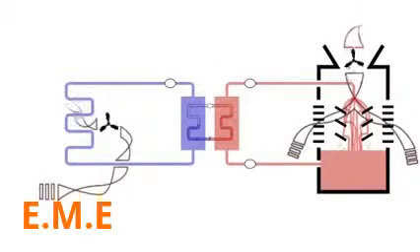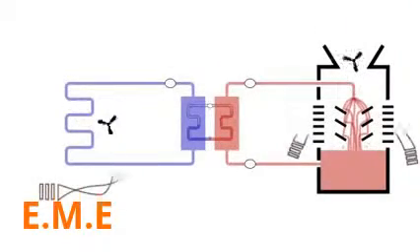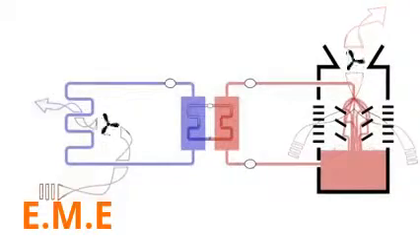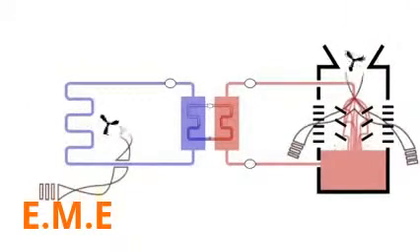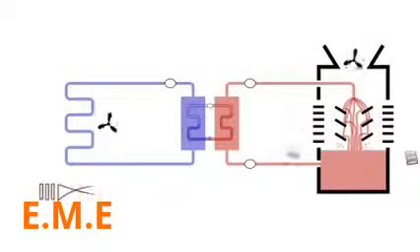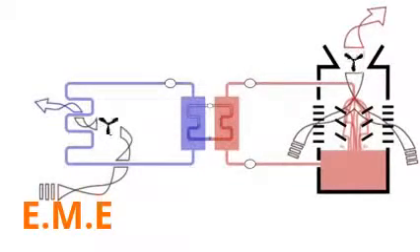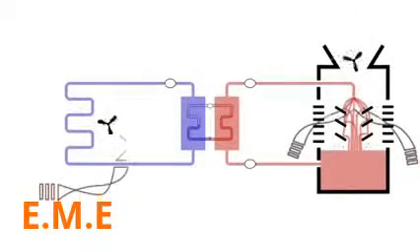This distribution network using water is complicated, but not exceptionally complex. Let's review. Water is cooled by the evaporator and distributed to the air handling units to cool room air. A separate loop of water cools the condenser and carries its heat to the outside air via a cooling tower.